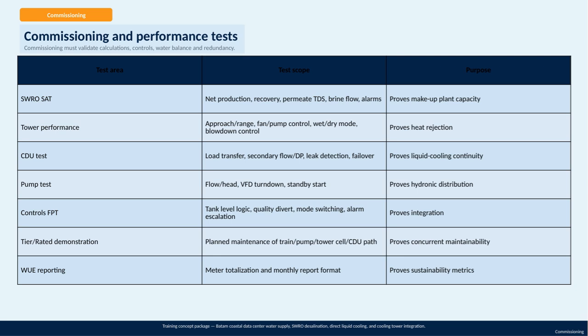Commissioning involves validating key aspects like calculations, controls, water balance, and redundancy to confirm everything functions as intended. Our training concept package focuses specifically on the Batam Coastal Data Center's water supply, incorporating SWRO desalination, direct liquid cooling, and cooling tower integration. Looking at the test areas in detail.